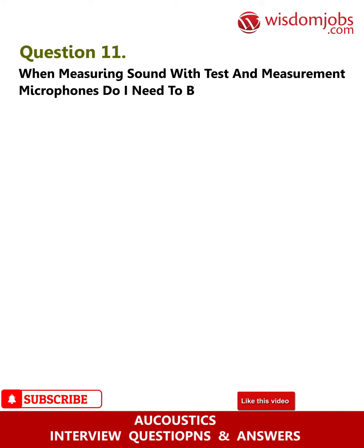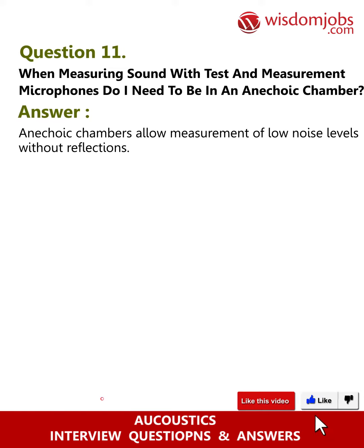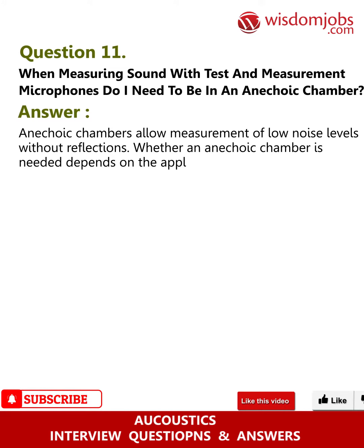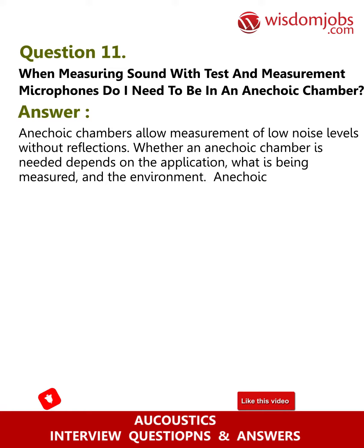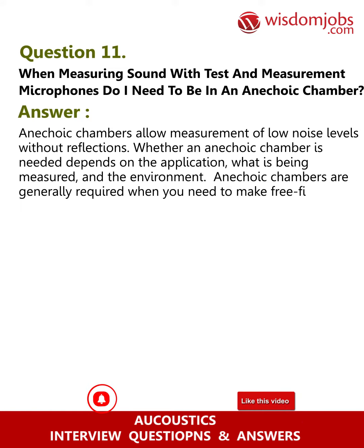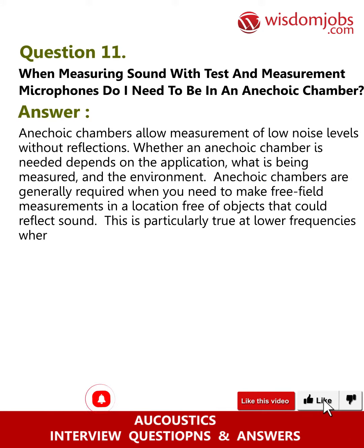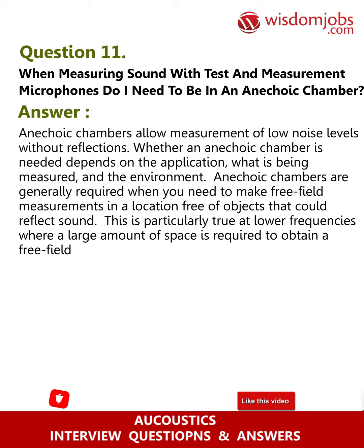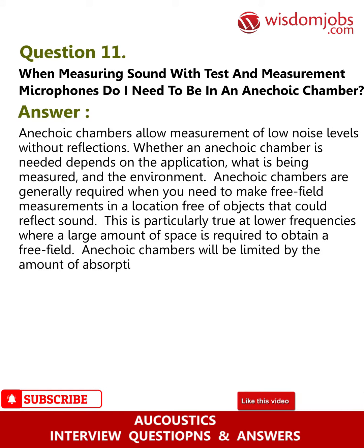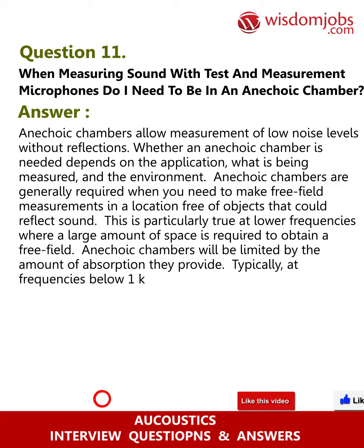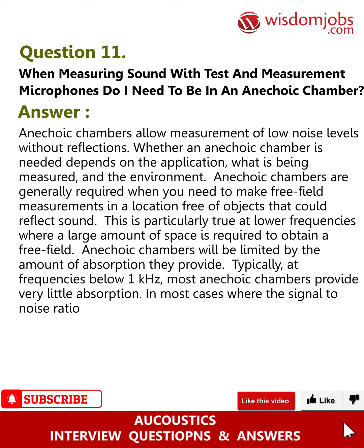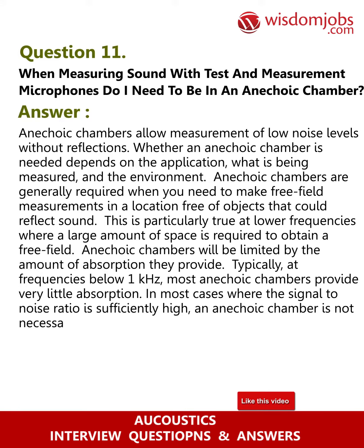Question 11. When measuring sound with test and measurement microphones, do I need to be in an anechoic chamber? Answer. Anechoic chambers allow measurement of low noise levels without reflections. Whether an anechoic chamber is needed depends on the application, what is being measured, and the environment. Anechoic chambers are generally required when you need to make free-field measurements in a location free of objects that could reflect sound. This is particularly true at lower frequencies where a large amount of space is required to obtain a free field. Anechoic chambers will be limited by the amount of absorption they provide. Typically, at frequencies below 1 kHz, most anechoic chambers provide very little absorption. In most cases where the signal-to-noise ratio is sufficiently high, an anechoic chamber is not necessary.